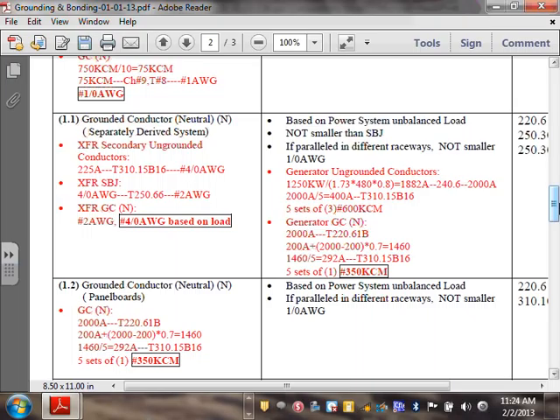Grounded conductor, neutral, at the separately derived system secondary, you size it based on the secondary ungrounded conductor. Here's the number 4/0 that we sized. System bonding jumper is number 2. Then the grounded conductor cannot be less than the system bonding jumper. Does that sound familiar? Isn't that what we did with the main, like with the main bonding jumper?